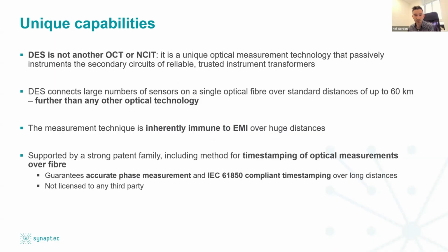The first important thing to say is that DES, distributed electrical sensing, is not just another optical CT or NCIT, which I'm sure you'll all have heard of and which have been offered by a range of manufacturers over the last couple of decades and have not really succeeded in taking off to any great extent. So we are not that type of optical measurement. As I've mentioned, what our method does is passively instrument the secondary of standard instrument transformers, allowing you to install those in new locations. So we use a fundamentally different physics to OCTs or NCITs.